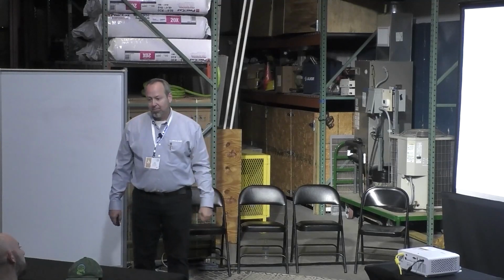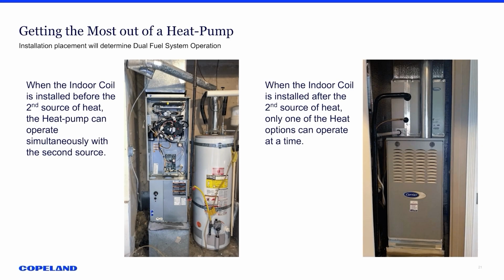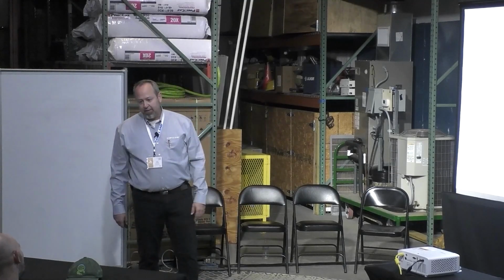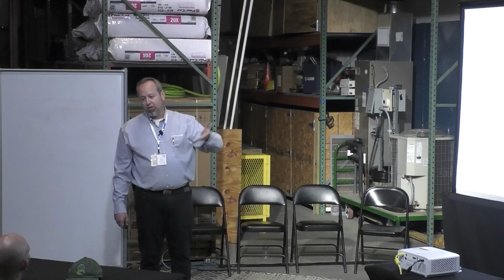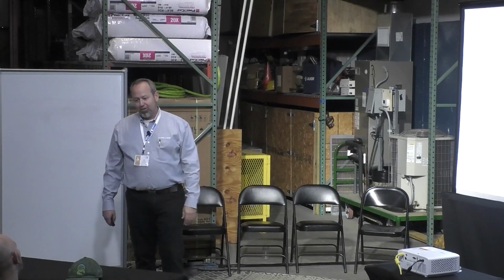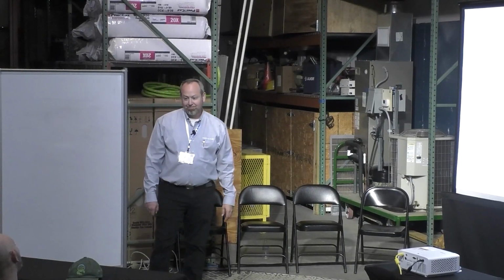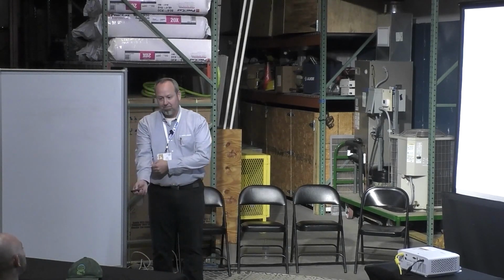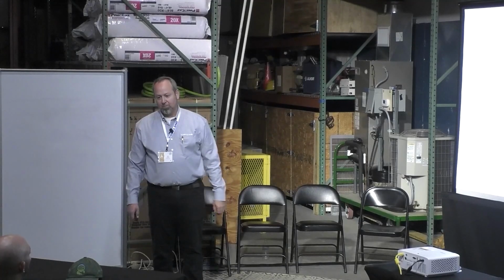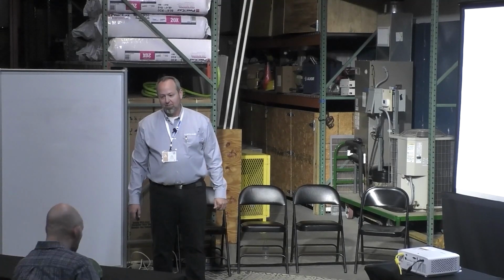What would be the advantage of the picture on the left? What would be the advantage of being able to run your heat pump and your gas at the same time? It's your auxiliary heat. So if you don't do that, when you go into defrost mode, what are you going to do? Well, that's another question I had too. When you go to defrost, I guess I did have that general question.